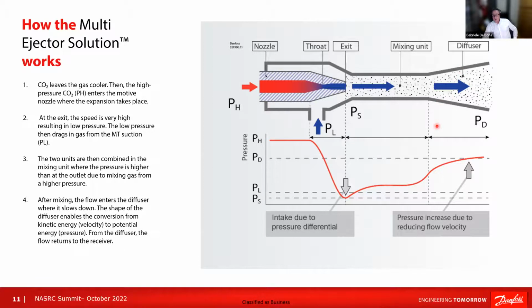The ejector technology is not new, as it dates back to the 19th century. What is new is its application in a refrigeration system. The dimensions of the diffuser, the mixing unit, and the nozzle are strictly related, and if this relation changes, the performance of the ejector decreases drastically. That is why we operate with different ejectors in parallel inside the same unit, and we are able to change the capacity of the block itself without losing the performance of the component.